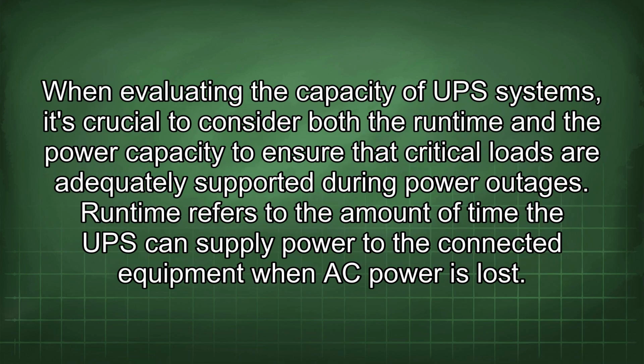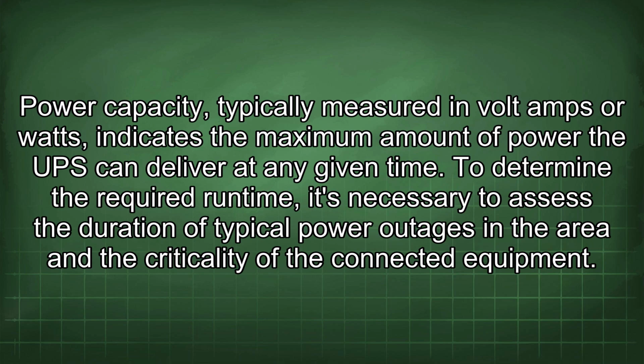When evaluating the capacity of UPS systems, it's crucial to consider both the runtime and the power capacity to ensure that critical loads are adequately supported during power outages. Runtime refers to the amount of time the UPS can supply power to the connected equipment when AC power is lost. Power capacity, typically measured in voltamps or watts, indicates the maximum amount of power the UPS can deliver at any given time. To determine the required runtime, it's necessary to assess the duration of typical power outages in the area and the criticality of the connected equipment.